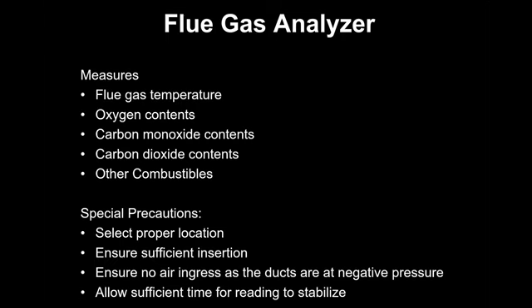Then we come to the flue gas analyzer. A flue gas analyzer will basically measure temperature, oxygen, and carbon monoxide. Then, of course, there are probes available which will measure NOx, SOx, and all that. That can be added if required. But from an energy audit point of view, the most critical things are temperature, oxygen, and carbon monoxide. Carbon dioxide content is normally calculated in electronic gadgets. It is derived based on the fuel composition. So in most instruments the carbon dioxide content is not correct, because it all depends on the composition of the fuel.